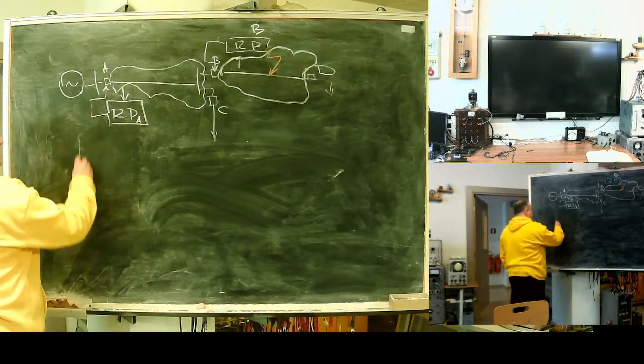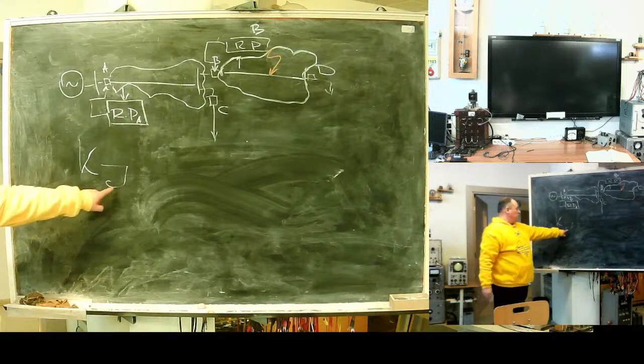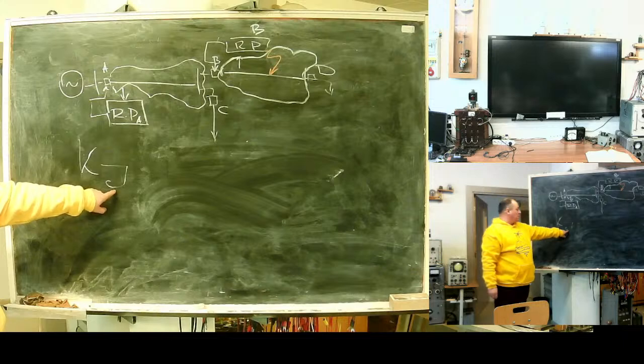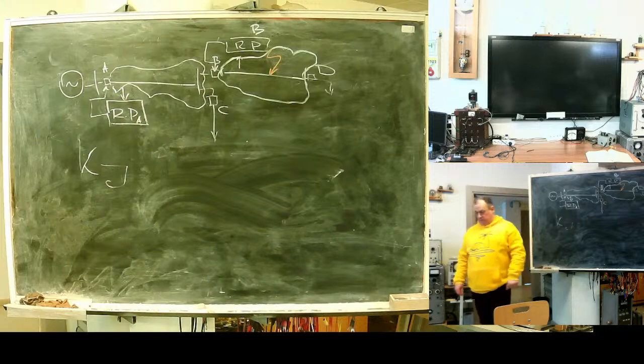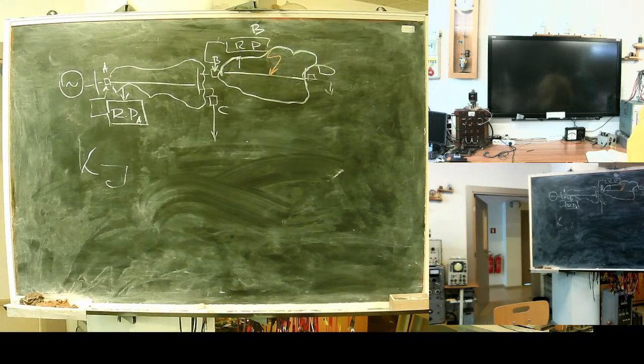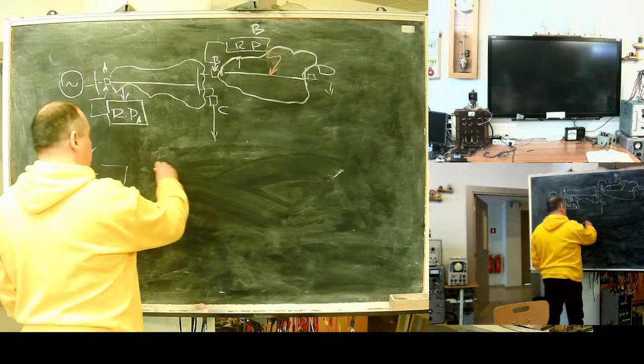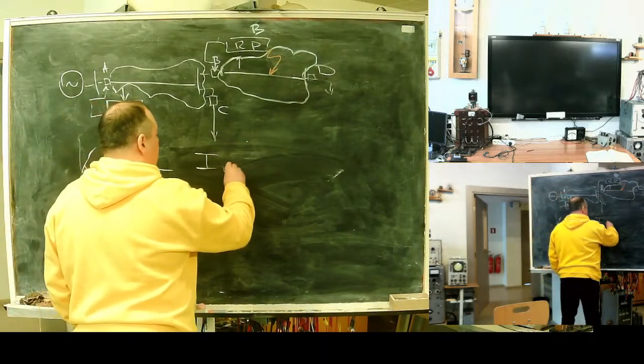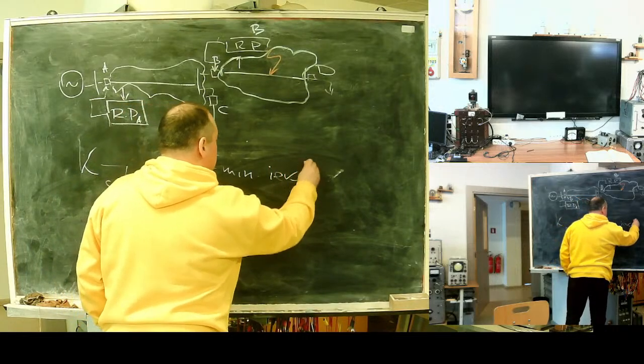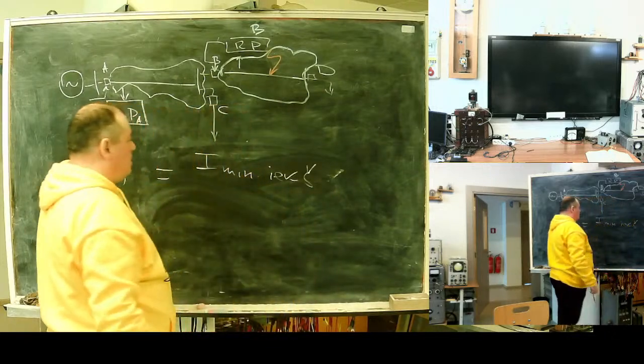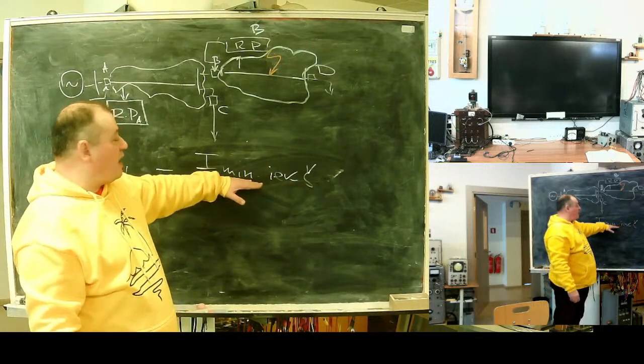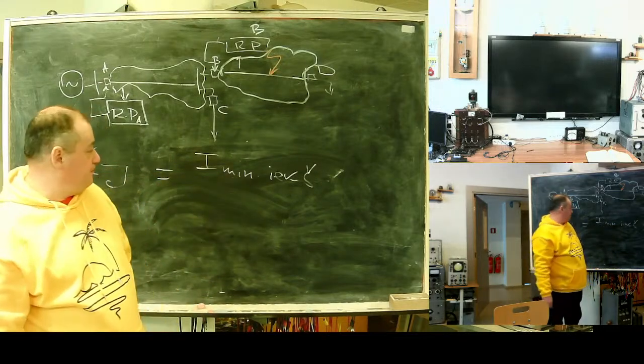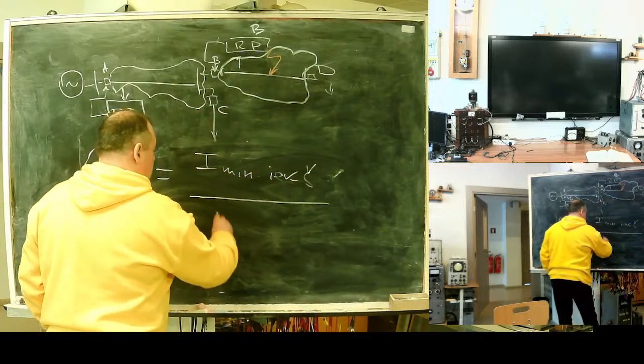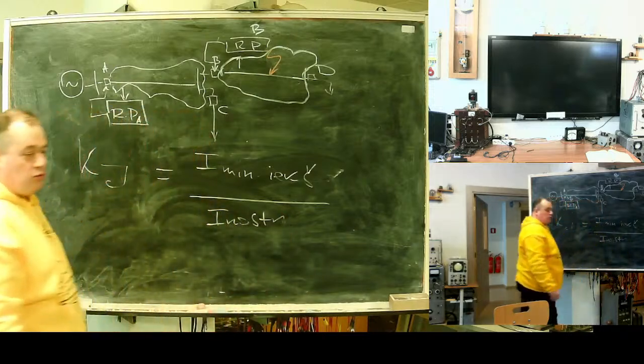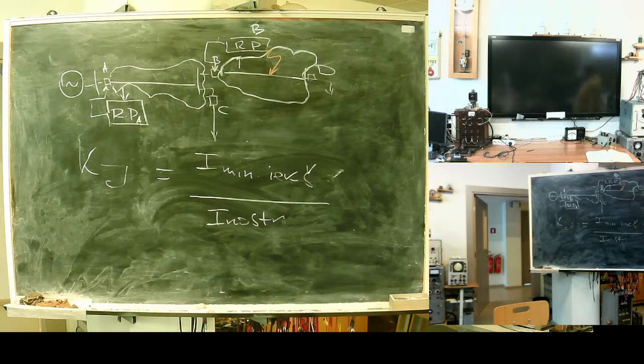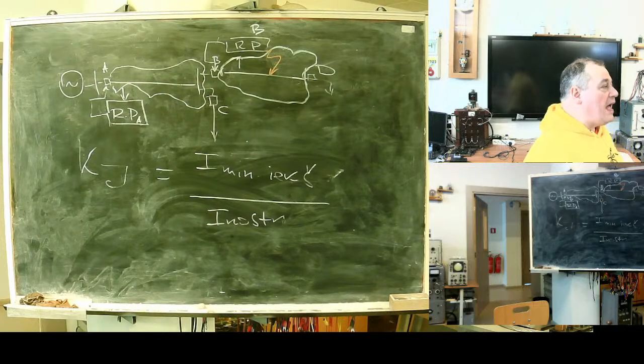Another one can be characterized; I will use this designation. In Latvian, jutīguma koeficients means sensitivity factor. It's used to evaluate or rate a protective device. It is the current of the minimal possible internal fault, divided by the nostrāde. What is nostrāde? It's the trip current. It's the threshold when relays disconnect. Threshold current. No, it's not a fault current.